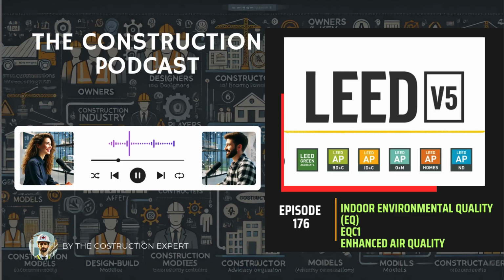That numerical specificity, ppb, it really speaks volumes about the level of air chemistry control required here. Why the emphasis on parts per billion for ozone? Because ozone is such a powerful oxidant and irritant, even very tiny concentrations, measured in parts per billion, can be irritating to the respiratory system or trigger asthma attacks in sensitive individuals. Maintaining a design target of 10 ppb is essentially aiming for background noise level, close to what you might find in truly pristine outdoor air, far from pollution sources. So how does a design team ensure they stay below 10 ppb?